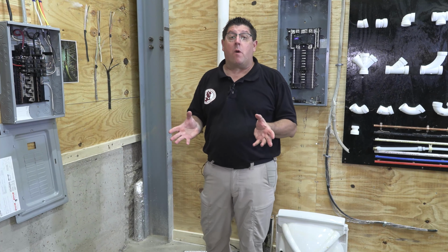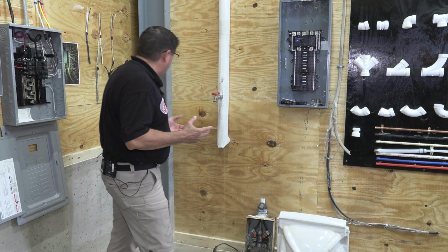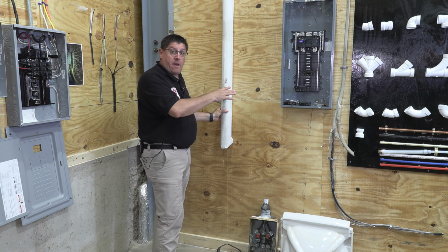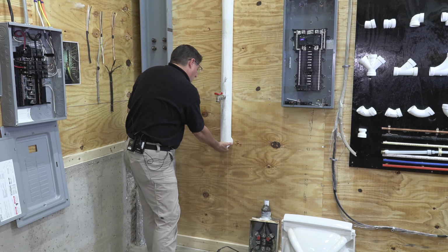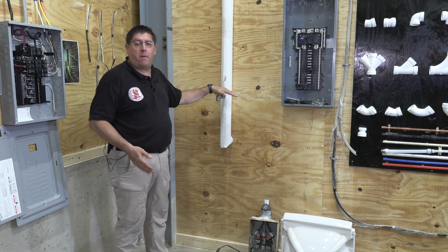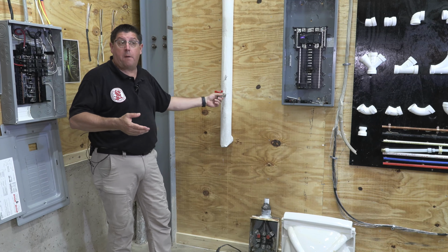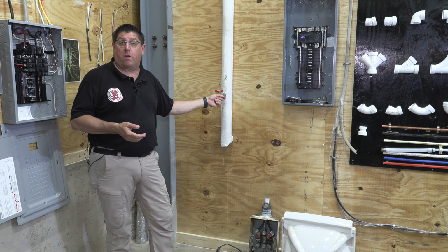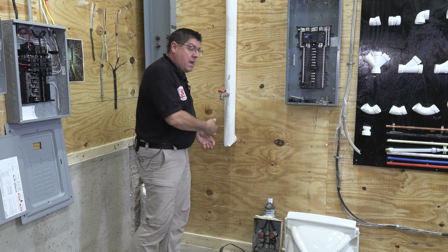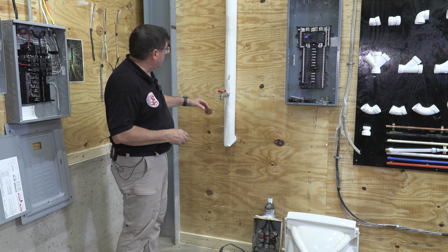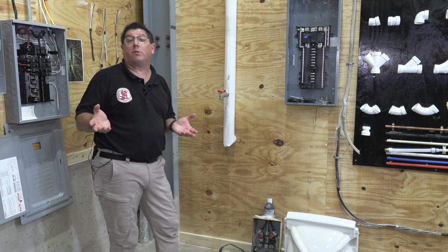While following the main water supply system, we see that it's left the other area, gone through the backflow preventer, and comes up through here. We've got a primary sillcock here. This is basically for two reasons. One, it helps drain the system if we're doing any plumbing work. And two, you could also use it as a convenience hose. But in this case, this is a warehouse space.